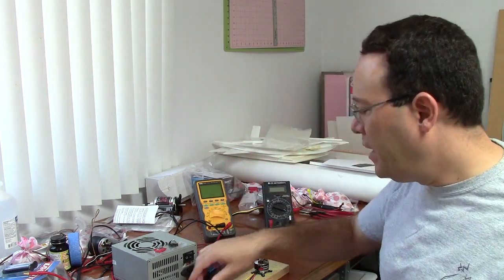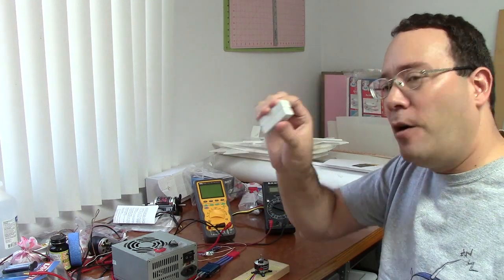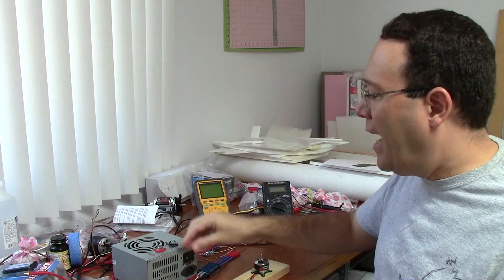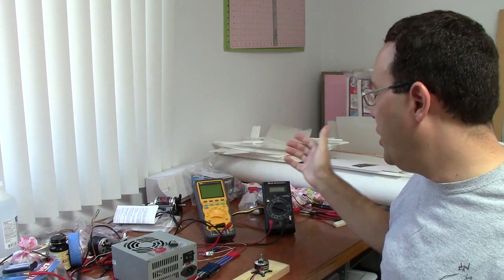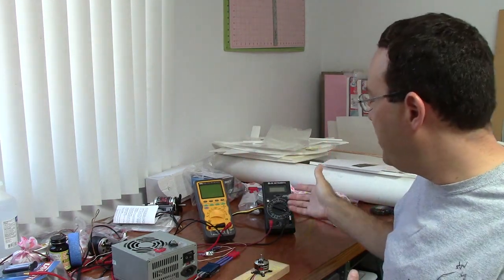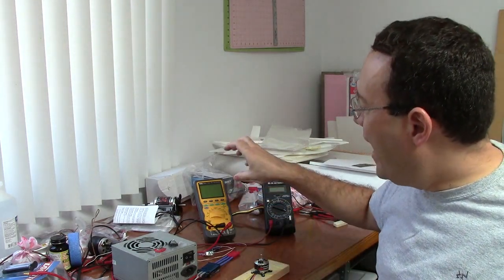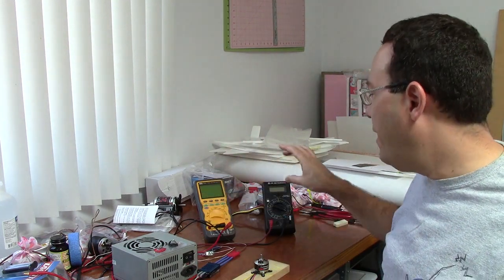I like to use my two multimeters, one for voltage, one for current. So I hook up my power resistors in series with the winding. I hook up my power source as input. Then one multimeter is measuring voltage, the other one is also in series with the circuit to measure the current. Wait a little bit to get a steady state, and then write down the values. If you take the voltage and divide it by the current, you get the resistance in ohms, and that will be the reading.